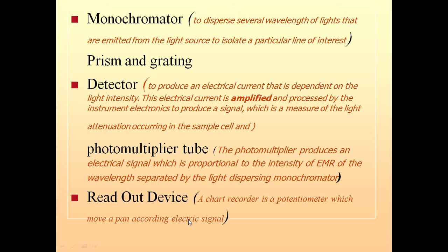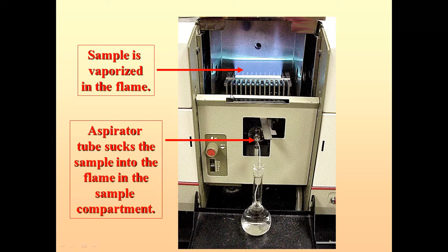This is how the sample is taken. This is the reference material. Sample is there. This is the capillary. Sample gets sucked. This tube sucks the sample in the flame into the compartment, and in between there is air and acetylene which is the fuel, gets burned, and this is the burner. The flame you are getting is a clean blue flame, where the sample gets vaporized.